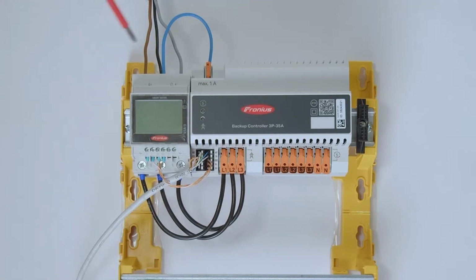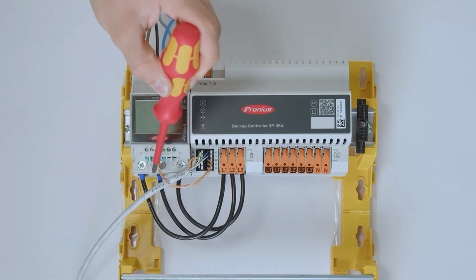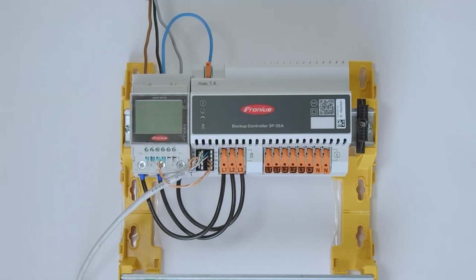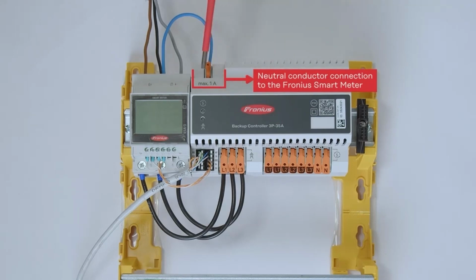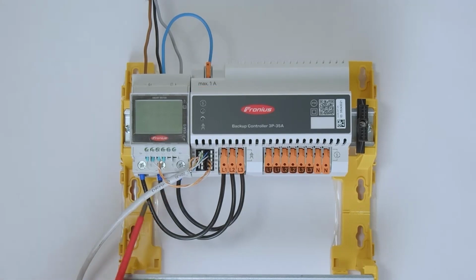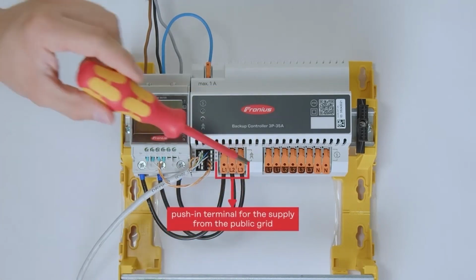Please also note the installation requirements for the Fronius smart meter, and especially, for example, the protective cover that excludes the data communication line from the phases. Please also watch the quick installation guide of the Fronius smart meter. There you also find, for example, the neutral conductor that is needed for the measuring point, and therefore we have a very convenient function here. Since you can use the neutral conductor coming directly from the backup controller, it is noted here with a maximum of 1 amp, and you can directly install the neutral conductor clamp here coming to the Fronius smart meter to make sure that you don't need an extra clamp or extra cabling. Furthermore, we now go three phases directly on the controller. Please also watch here the grid symbol.